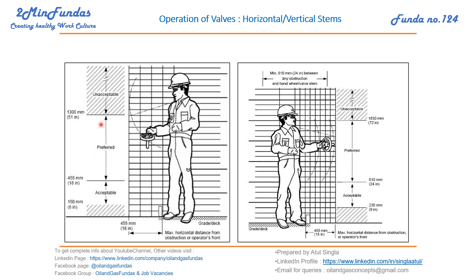Similarly, for valves with horizontal stems, the preferred elevation range is from 610mm up to 1800mm. So 610 to 1800mm is the preferable elevation of the stem for vertical valves with horizontal stems. Our main purpose is to provide ease to the operator while operating the valves.